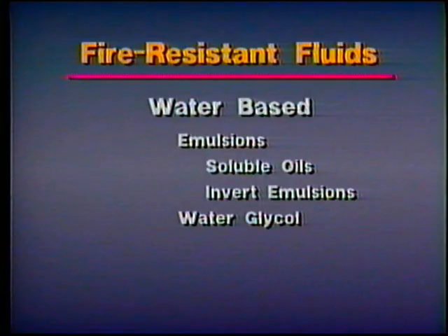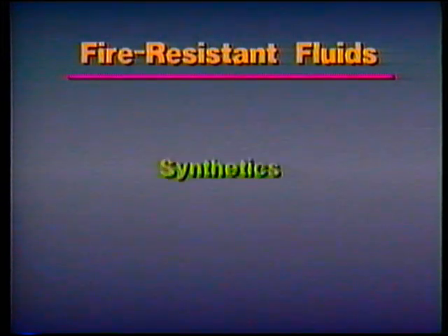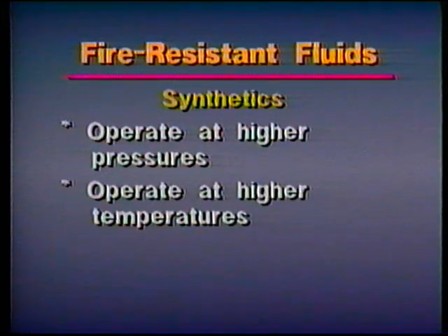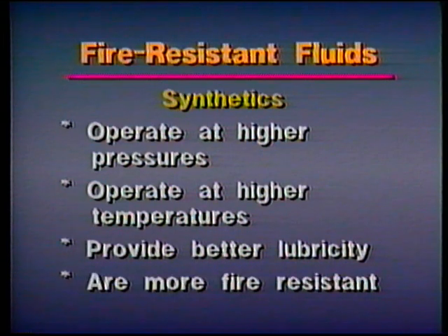The last category of fluids we need to discuss are the synthetic fluids. These man-made solutions operate at higher pressures and higher temperatures. They provide better lubricity and in many instances are more fire-resistant than emulsions. They do, however, cost more than most water-based fluids.